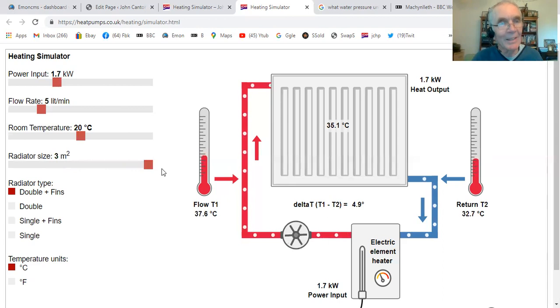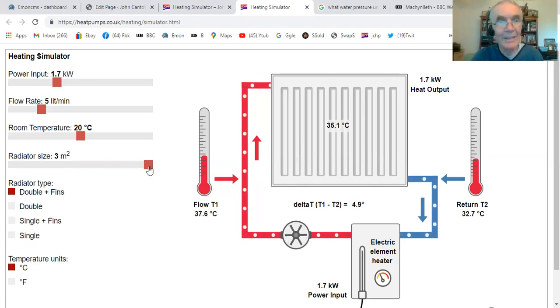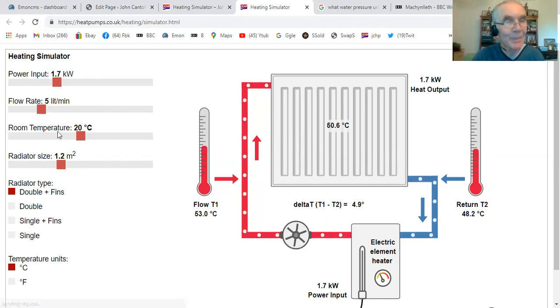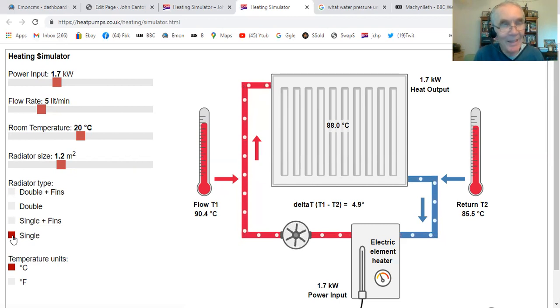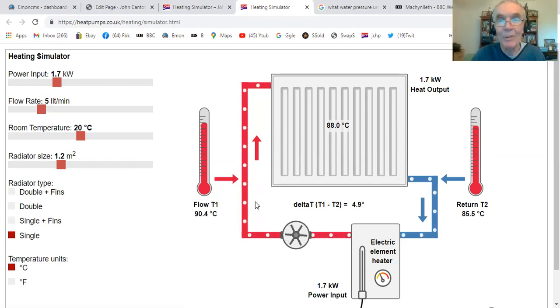Now let's go to the other extreme — a very big radiator. You won't easily find a three square meter radiator, but if you did, it would get down to 35 degrees, which is only lukewarm, yet it's still dissipating 1.7 kilowatts at a much lower temperature. Let's compare radiator types. We've got a double radiator with fins inside. If we go to an old single radiator, it jumps up to 88 degrees because that radiator isn't shedding heat so well, so it gets hotter — it has to, in an attempt to get rid of that 1.7 kilowatts.